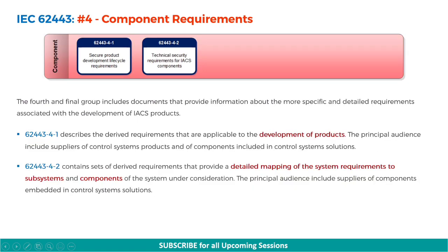The fourth and final section is Components Requirements, that is 62443.4. This group includes documents that provide information about the more specific and detailed requirements associated with the development of IACS products. 62443.4.1 describes the derived requirements applicable to the development of products, for suppliers of control systems products and components. 62443.4.2 contains sets of derived requirements providing a detailed mapping of system requirements to subsystems and components, intended for suppliers of components embedded in control systems solutions.